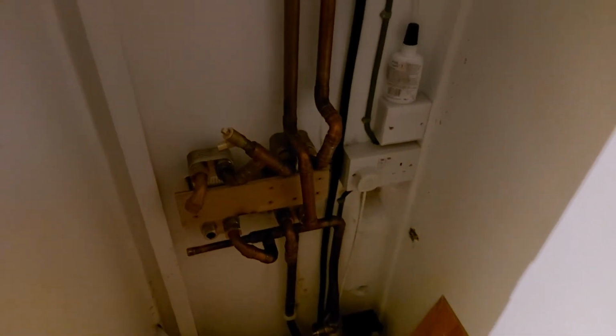Hi everyone, so tonight I'm heating the house using the wood burning boiler, and it's taught me quite a bit about sizing heat exchangers. You should use the biggest heat exchanger which will fit and which you can afford, because I think this heat exchanger was rated about 30 kilowatts, something like that. But that would be with freezing cold water in one circuit and roasting hot water in the other.